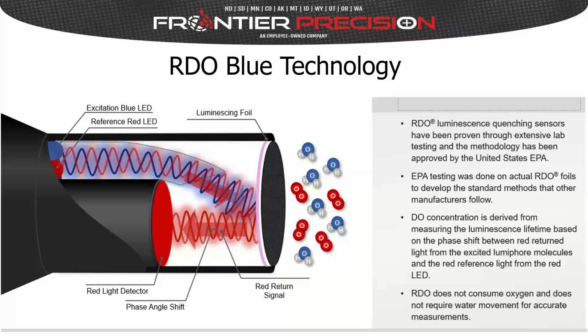quite inexpensive. It was a little bit maintenance intensive in that it required quite frequent calibration and replacement of those Teflon membranes. At least monthly with most people, sometimes more often, you had to take off the old membrane, put new dissolved oxygen electrolyte in that Clark cell between the anode and cathode, put a new membrane on there, hold it in place, and then recalibrate everything.